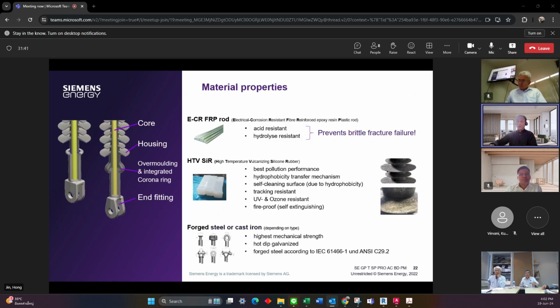We use a very high quality material. At the middle, the core material is ECR FRP rod, electrical corrosion resistant fiber reinforced epoxy plastic. Overmoulding is the direct molding of the silicone rubber, and this silicone rubber is HTV, high temperature vulcanizing silicone rubber. It's our standard technology and material. And on both sides, we have forged steel and cast iron as the end fitting.